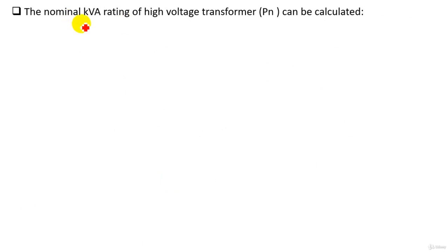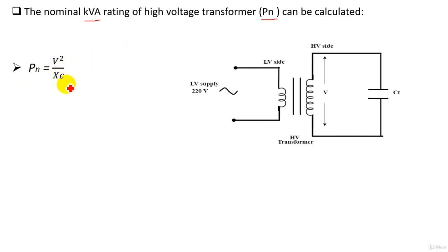Now we want to get the kilovolt ampere rating of the high voltage transformer. Now we want to get the rating of the transformer to be designed. The rating of the transformer is Pn, while Pn in kilovolt ampere. So how we can find the kilovolt ampere rating of the transformer? We know that Pn equals V square over Xc from this circuit, while V is the voltage of the high voltage side of the transformer, while Xc is the reactance of the insulation.